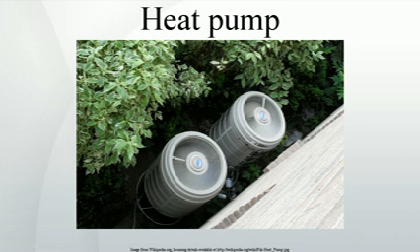Ground source heat pumps, also called geothermal heat pumps, typically have higher efficiencies than air source heat pumps. This is because they draw heat from the ground or groundwater, which is at a relatively constant temperature all year round below a depth of about 30 feet, 9 m. This means that the temperature differential is lower, leading to higher efficiency. Ground source heat pumps typically have COPs of 3.0 at the beginning of the heating season, with lower COPs as heat is drawn from the ground.